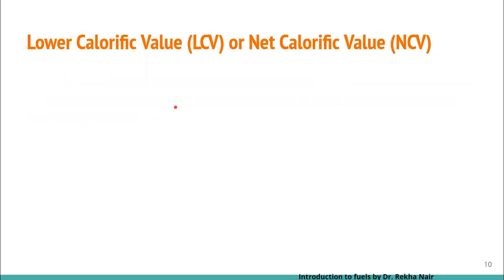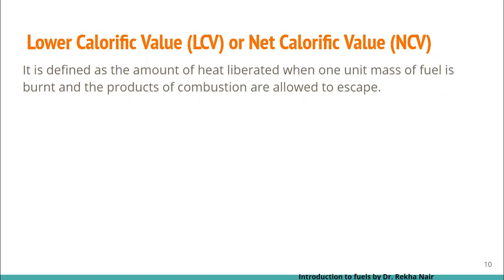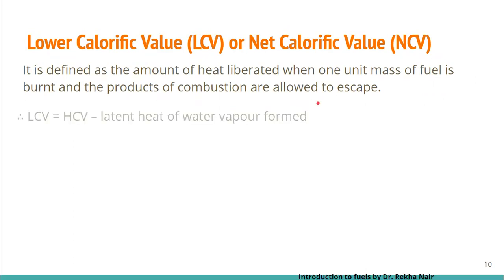The next calorific value is lower calorific value, which we also call net calorific value (NCV). This is defined as the amount of heat liberated when one unit mass of the fuel is burned and the products of combustion are allowed to escape. So LCV (or NCV) is equal to higher calorific value minus the latent heat of water vapor formed.